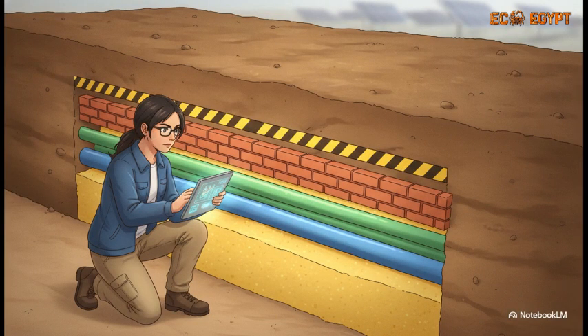Think of an underground trench like a highly engineered sandwich. You definitely don't just toss the cables in the dirt and call it a day. Starting from the bottom up, the cables rest on a precise 10-centimeter bed of pure sand, so they don't scrape against sharp rocks. Then, they're laid completely flat with exact separation gaps, and covered in another 20 to 30 centimeters of sand. Next comes the armor, rows of protection bricks. You're looking at 8 bricks per meter for the critical MV lines and 2 per meter for LV. Top it all off with bright danger tape 30 centimeters above the cable, and finally, compacted topsoil. Every single layer has a vital job.